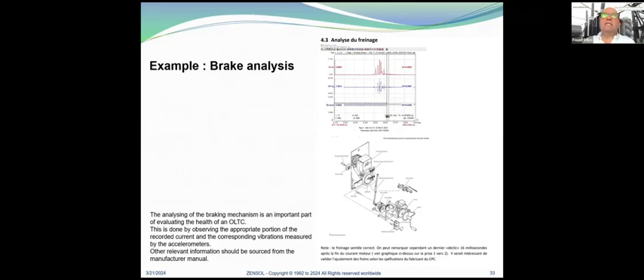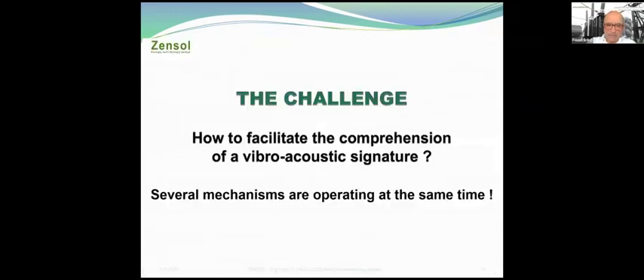What you have to analyze is the inrush current, the flat portion for the operation, and at the last the braking part of the current, and of course at the same time the impacts that you record. So now the challenge is how to facilitate the comprehension of a vibroacoustic signature. Several mechanisms are operating at the same time.